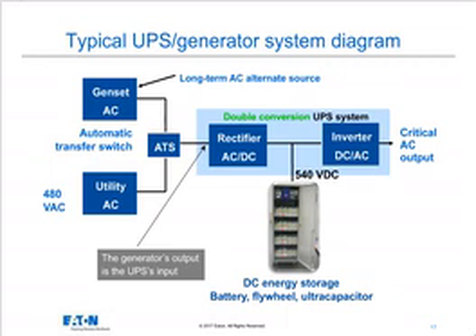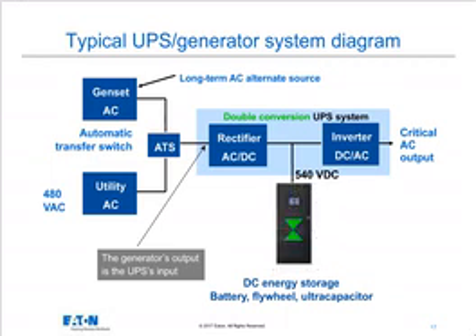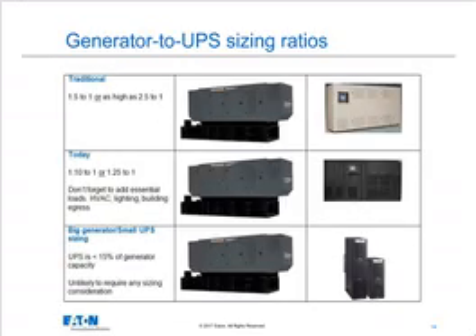And the benefit here for the end user is they don't have to oversize their generator as much as they did back in the olden days. If we look at the next slide, there's a table that shows that for most modern UPSs and generator sets today, here it comes. And this table shows at the top the way it was done traditionally with an older UPS and older generator. And as a result, you see that in many cases, it was necessary to make the generator from 2 to 2.5, sometimes even 3 times the size of the UPS that generator was supporting, plus all the other ancillary loads that you might be powering in the building, like air conditioning and elevators and emergency lighting and that type of thing.